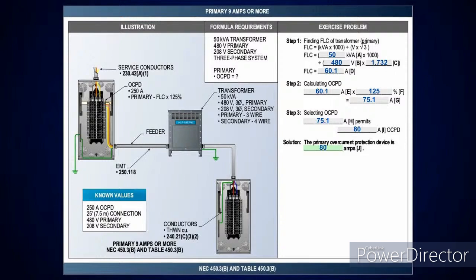Now, this is where you're looking at my voltages here, and you're going to see this is where I'm less than 1,000. Okay, so now you're going to flip over and look at table 450.3B. You'll just go to the next page, at the top left-hand side of that page. Now, what is the information that's important here? Well, I got a 50 kVA transformer. I got a 480 volt primary, and I'm doing primary only here. Okay, so I got 50,000 divided by 831 volts gives me 60.1 amps.